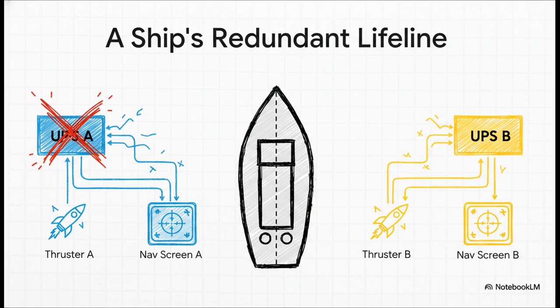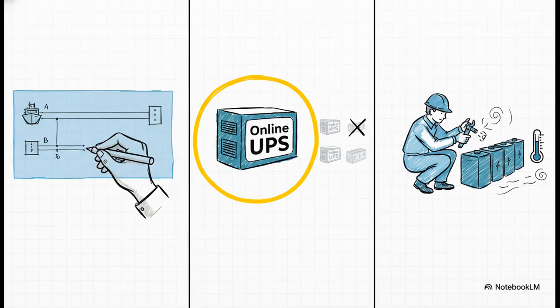They are physically and electrically separate. So if anything in the A system fails, the UPS, a cable, whatever, the entire B system just keeps on running without missing a single beat. Making sure that 1 second of darkness never comes isn't about some single magic box. It's this strategic dance of really smart system design, carefully selecting the right technology, and relentless, unforgiving maintenance, especially of those super temperature-sensitive batteries.